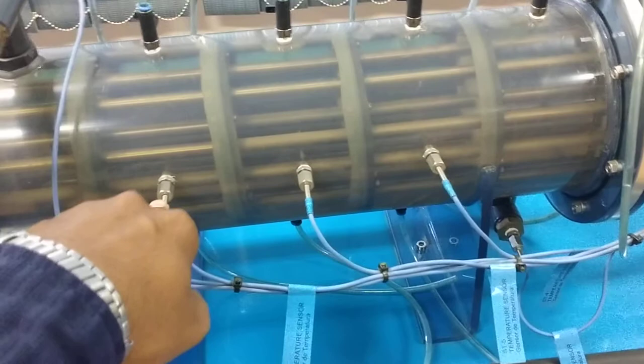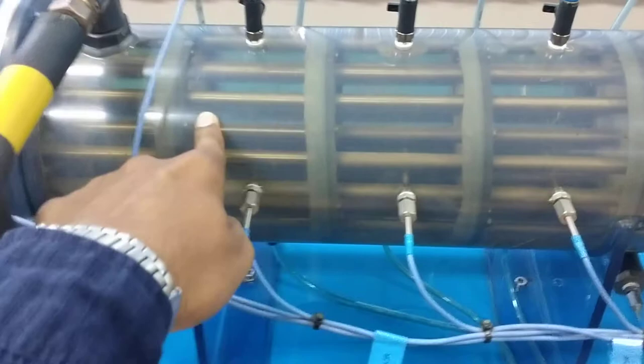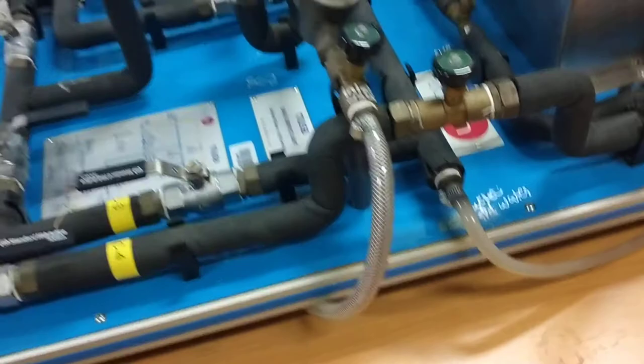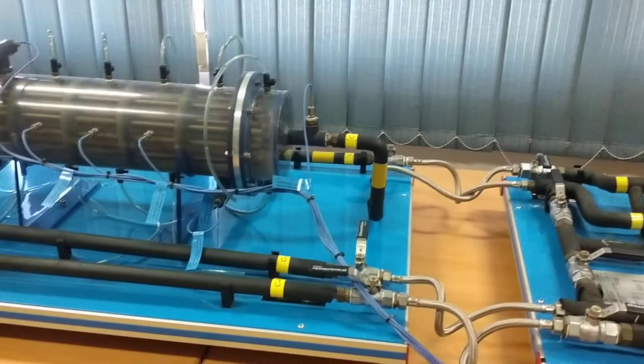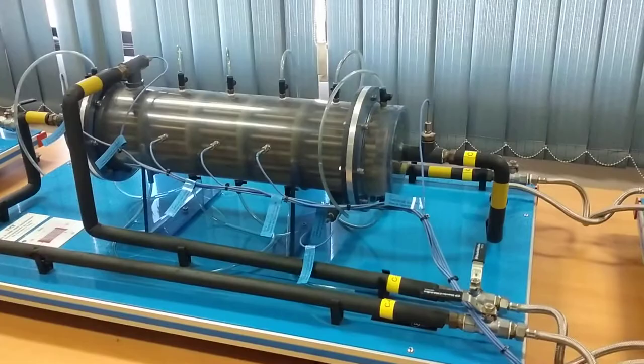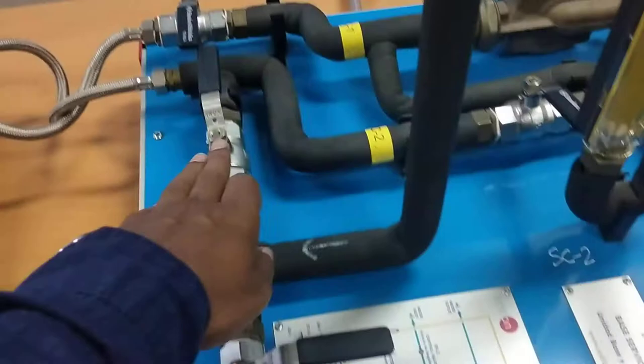So you can see the baffle plates here to create turbulence in the flow of the cold water. And then the cold water exits from this point, takes this path, and from here it moves to the sink. Okay, these are the major parts and configuration of the shell and tube heat exchanger. To set the flow of the cold water in parallel flow, what we have to do is just close these two valves here and open these two valves.